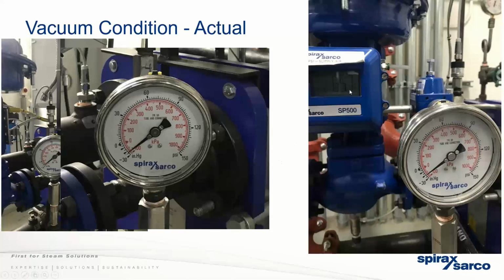And this is under a fairly high load. The control valve is open 65%, and we can still achieve vacuum. So we're at 20 inches there. The point of this is to design your heat exchanger as efficient as possible.